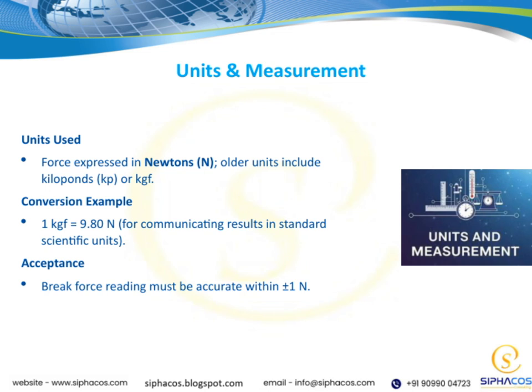Another key point is the acceptance criteria for break force readings. To ensure accuracy and reliability, the readings must be within plus or minus 1 newton. This level of precision is crucial for consistent and valid results. Overall, understanding the units used and maintaining measurement accuracy are fundamental to obtaining valid and meaningful data in our testing process.